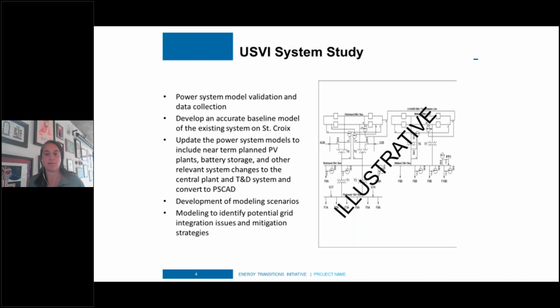And over the last month, we have been doing a number of simulated transient events in order to collect data that we can use to validate the model of the system and help with system integration studies. So we were able to take their existing PV system offline, which is about 5 megawatts. We dropped the desalination plant, which is a reverse osmosis plant. They took one of their generators offline, and even tripped out a distribution feeder.